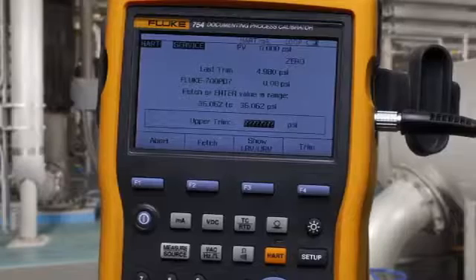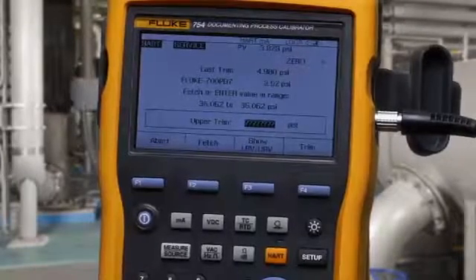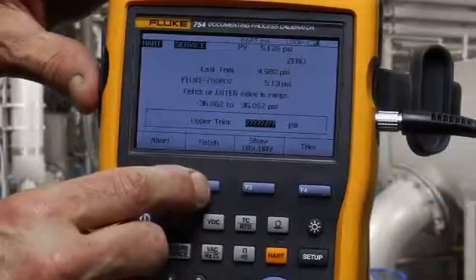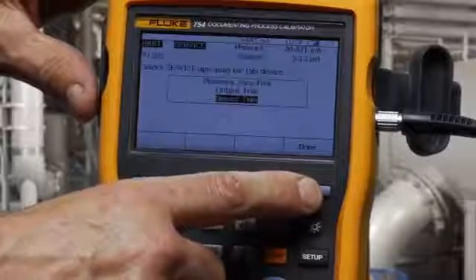Pump to full scale, which is 5 PSI for this device. See the pressure noted here, approximately 5 PSI. Fetch and trim. Done. And done.